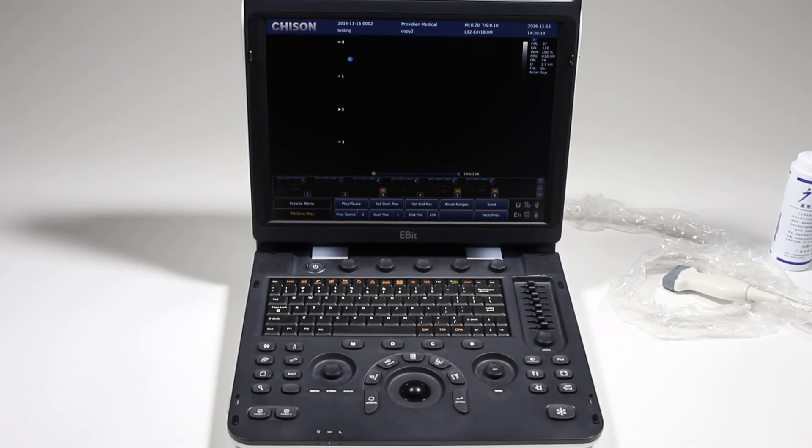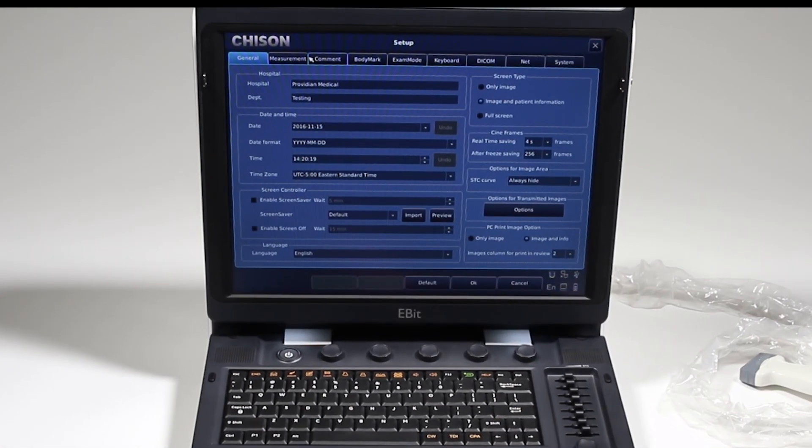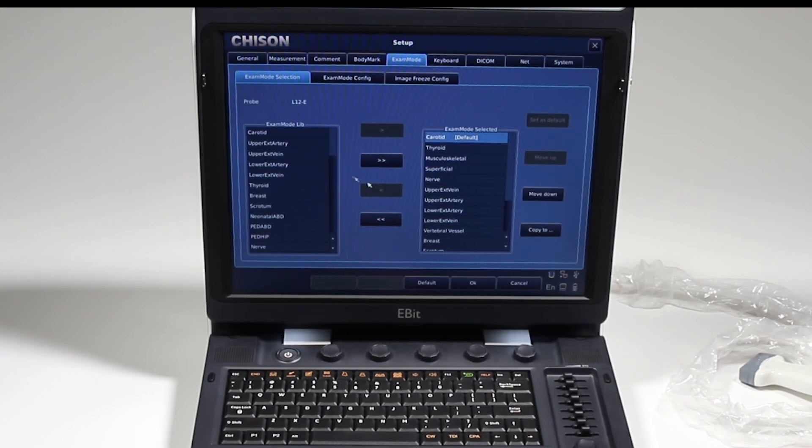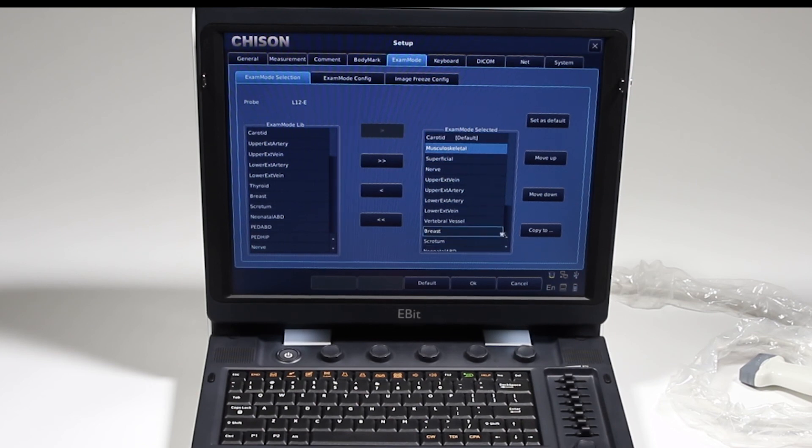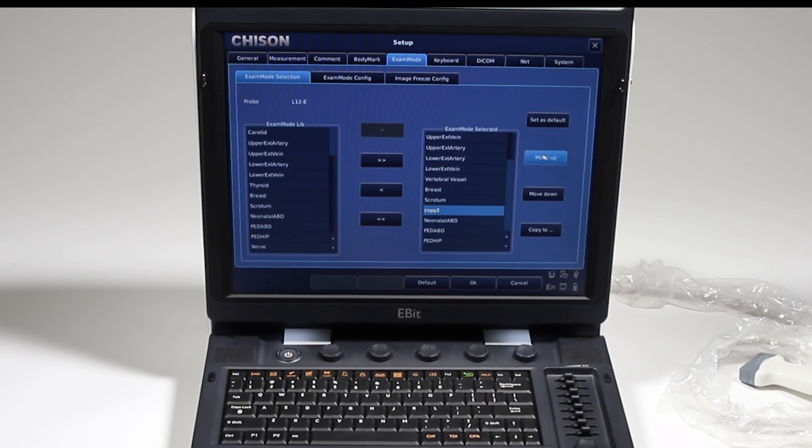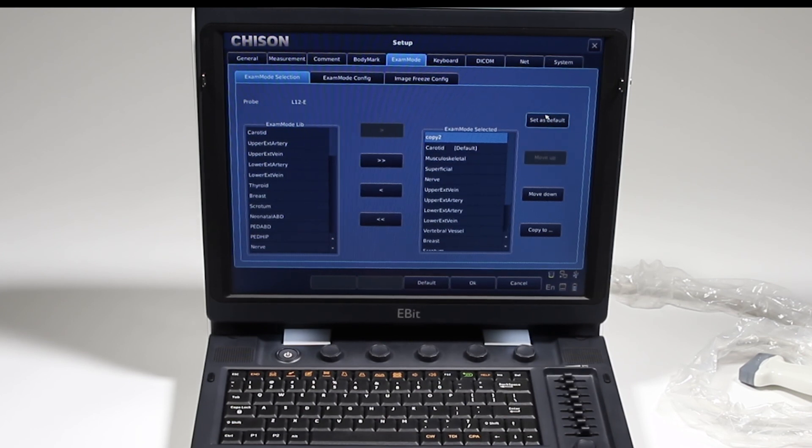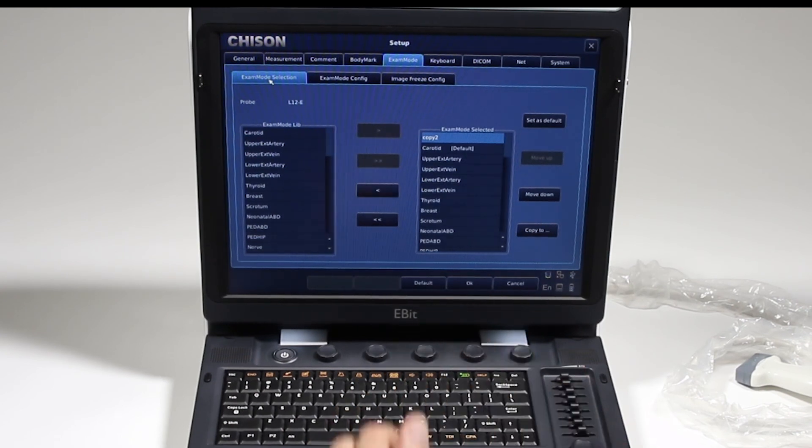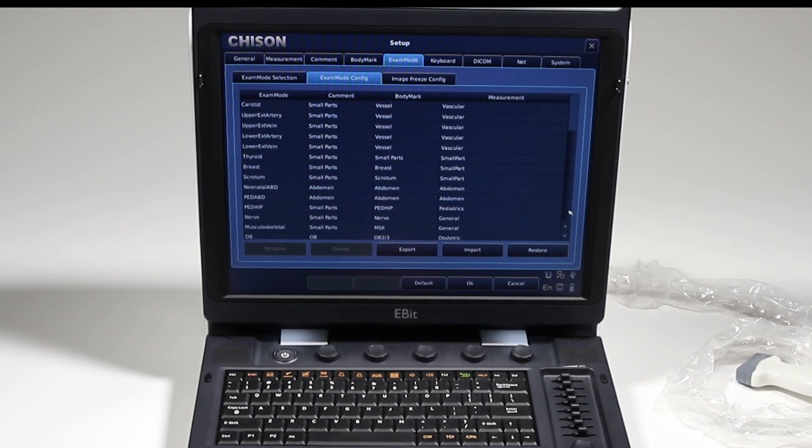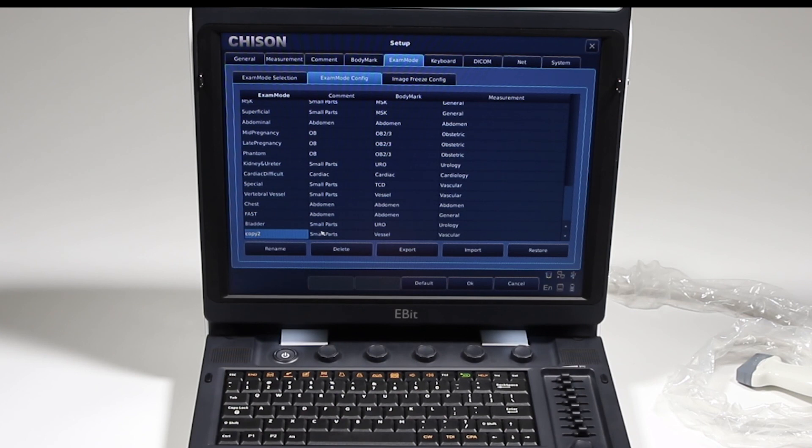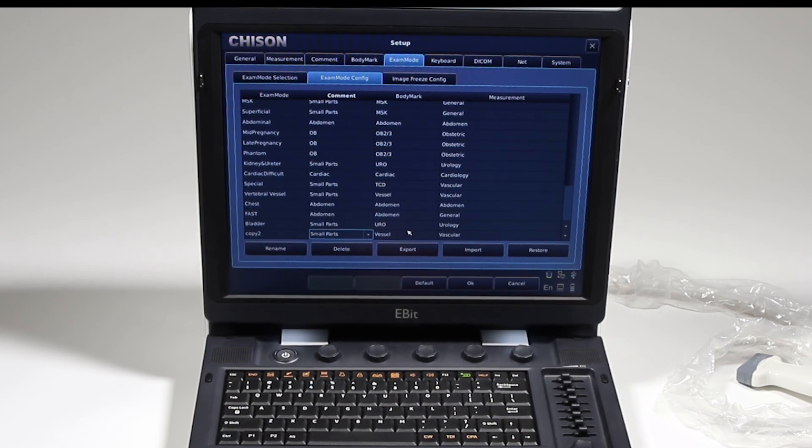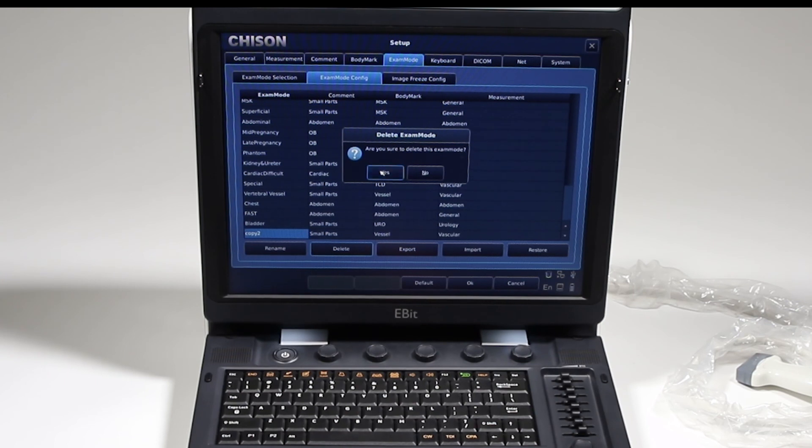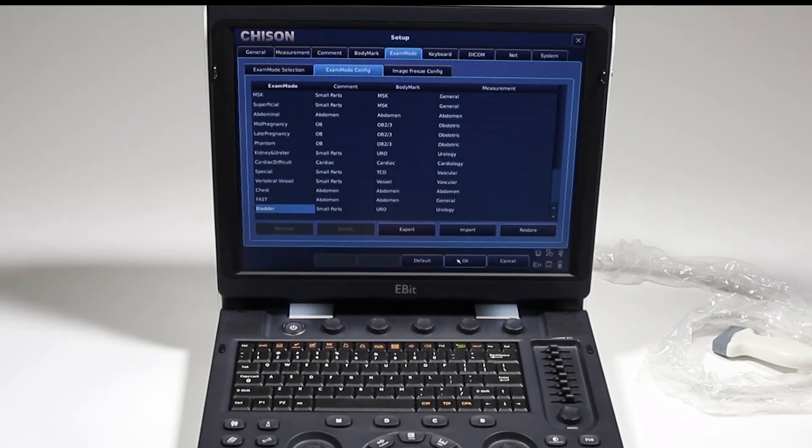Now if we want to adjust where that preset is, we'll get into this later. But just to show you real quick, we can go to our exam modes here and we can set our default. We can add or remove various ones. Say if I don't want thyroid, I can go ahead and click that and it removes from this menu here, which will be the menu I see when I press that exam key. See how copy to, the one I created, is at the very bottom. I can move that all the way up to the top and also set it as the default. Now if I mess that up and I want to get rid of it, I can go to this exam mode config, scroll down, get rid of this. I can also change the comments library for that preset, body markers and what measurement do I want to appear. I'm just going to go ahead and delete that because I don't want that setting. Yes, I want to delete it and it's gone. I'm going to click OK.